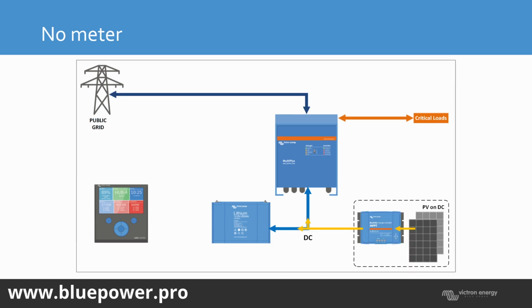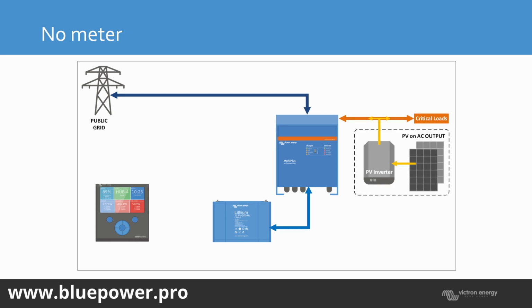Other types of systems we can do is a no meter system. So we're not monitoring any of our non-essential loads, or we don't have any non-essential loads on site, and we're running our critical loads from battery power and PV power. As well, we can also do that with an AC coupled PV system and feed our critical loads from PV power and charge our battery from the PV power. Just note, if you don't have a compatible PV inverter that communicates with Victron and you are connected to the grid, any excess power is going to be pushed into the grid. So it's only the Fronius and ABB inverters that I know of that have the communication with Victron that prevents feed in while connected to the grid without any extra meters or anything.